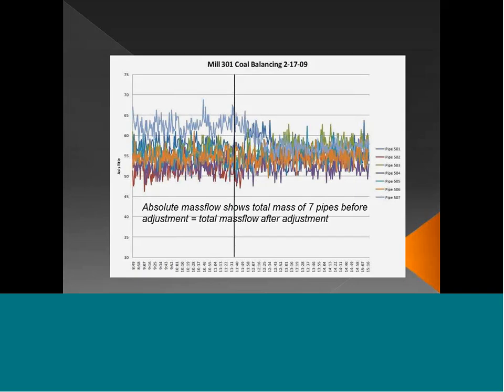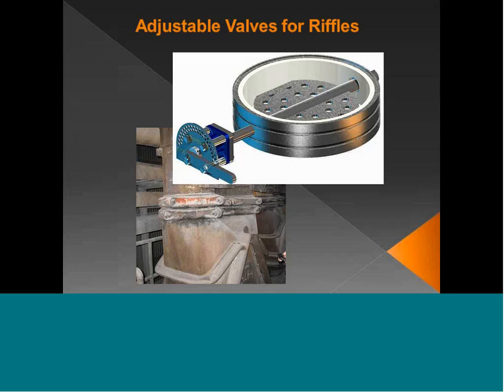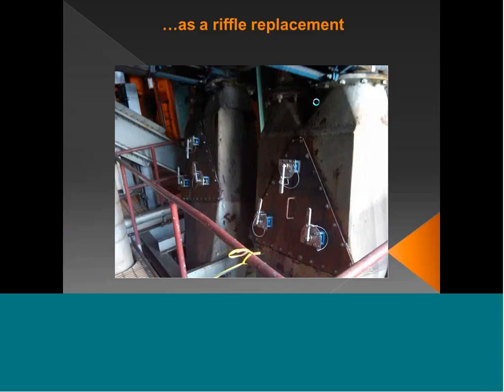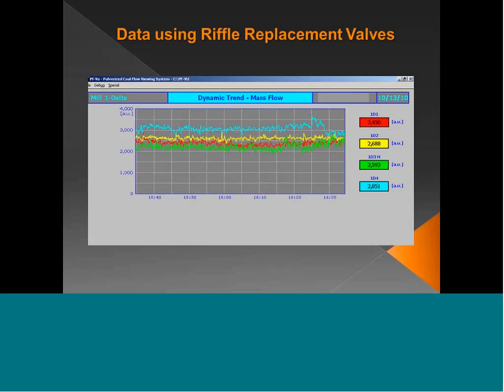Coal valves have been developed specifically for T-fired units that use, or some wall-fired units, I guess, as well, that use riffles. In this case, you can see that on the outlet of this particular riffle, they typically use fixed orifices. We can replace that fixed orifice with this adjustable orifice. Or in a case like this, where pressure drop was a very big concern to the plant, they didn't want to introduce any more pressure drop. They were primary air limited. We eliminated the riffle that was in this riffle housing, and we put in this new riffle door with valves built into it. And this is the data from balancing using that device. So there are multiple means of balancing coal on exhauster mills and pressurized mills.